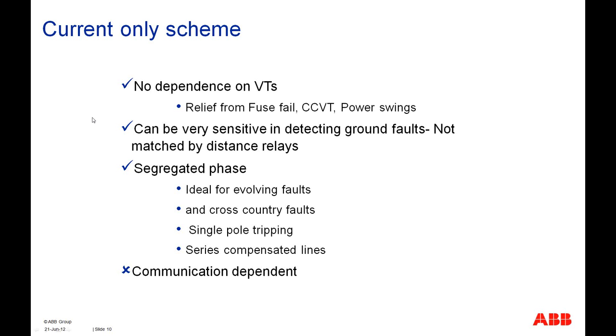As it calculates the differential as well as the stabilization current values per phase, the information is phase segregated, and it is then ideal for evolving faults as well as for cross-country faults. And as we have the measurements on a phase segregated basis, we can have single pole tripping as well. And because it is not dependent upon measuring the impedances of the line, series compensated lines will also have no impact on the line differential protection scheme.